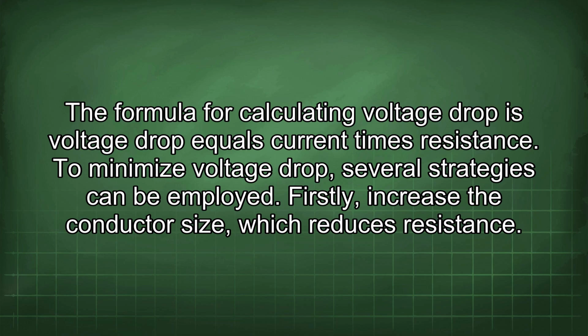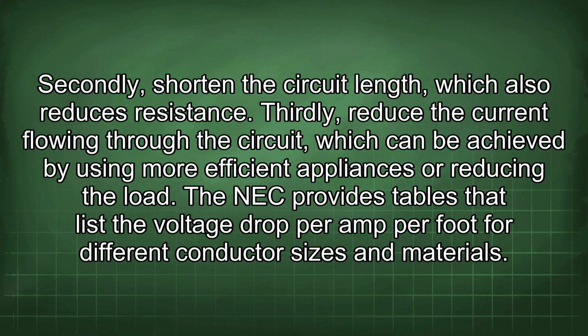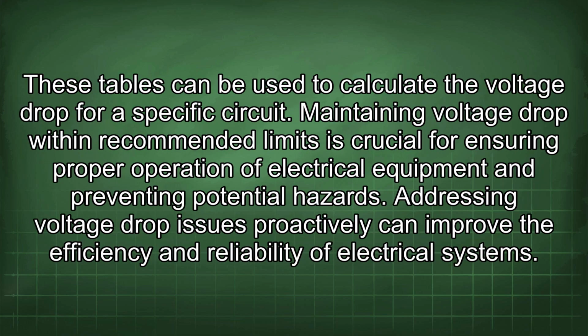To minimize voltage drop, several strategies can be employed. Firstly, increase the conductor size, which reduces resistance. Secondly, shorten the circuit length, which also reduces resistance. Thirdly, reduce the current flowing through the circuit, which can be achieved by using more efficient appliances or reducing the load. The NEC provides tables that list the voltage drop per amp per foot for different conductor sizes and materials. These tables can be used to calculate the voltage drop for a specific circuit.